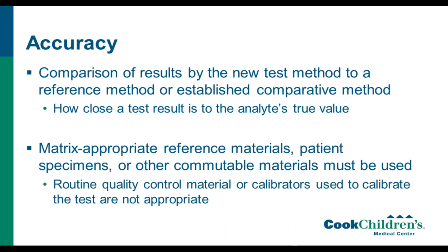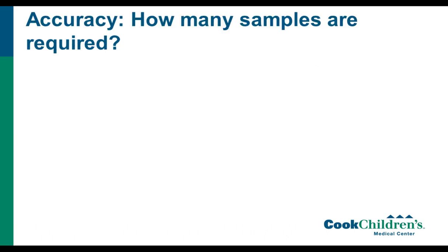You want to use matrix appropriate materials, and preferably for accuracy studies, patient specimens are best. That may not always be possible depending on what the assay is and what your lab has available, but you can also use matrix appropriate reference materials or other commutable materials. However, CAP specifically defines that you can't use routine quality control material or calibrators that are used to calibrate the test. So primarily patient specimens, but you can use reference materials as well if necessary. We'll talk about places to get some of those in just a moment.